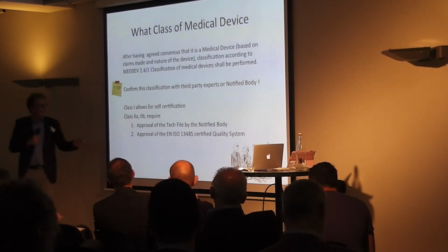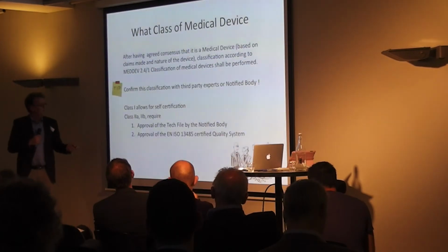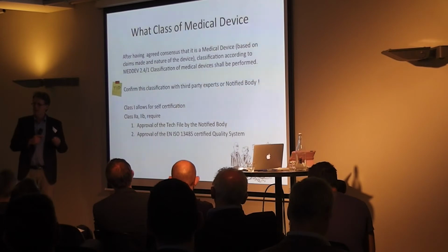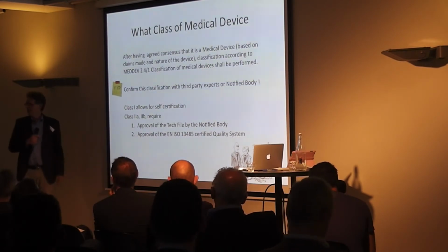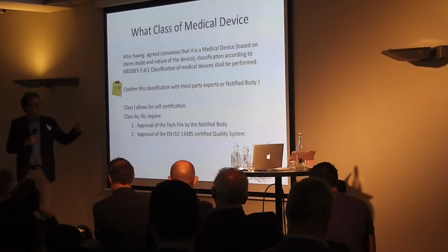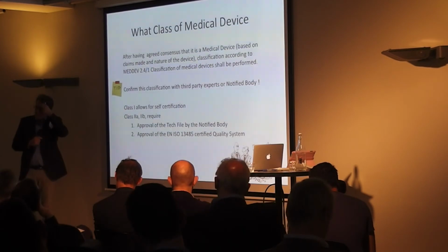Yeah, the class 1 devices, basically there's a category, this is the class 1, which is the majority of these products. The 1S, the S stands for sterile. So if you bring a sterile product on the market, there are specific requirements related to the sterility.